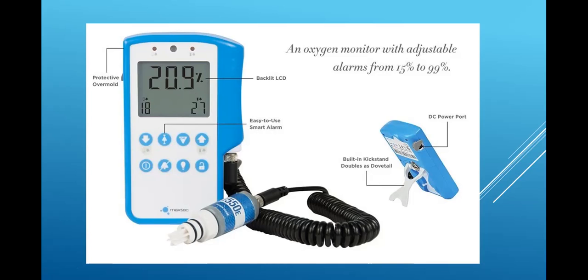When I break it out for the day, I have to calibrate the oxygen analyzer at least once per shift, okay? So when I bring it out, I need to calibrate it first, all right? So I will calibrate it to room air and to 100%. Because if I put it in 100% and it's reading 93, I have to adjust it up to 100%. If I take it out and put it in room air and it's reading 18 or 23 or something like that, I just adjust it till it gets to 21, okay?